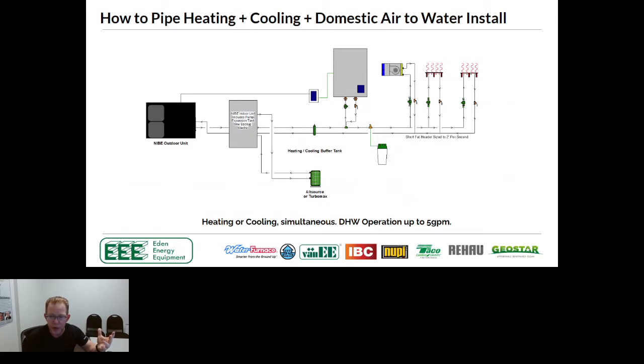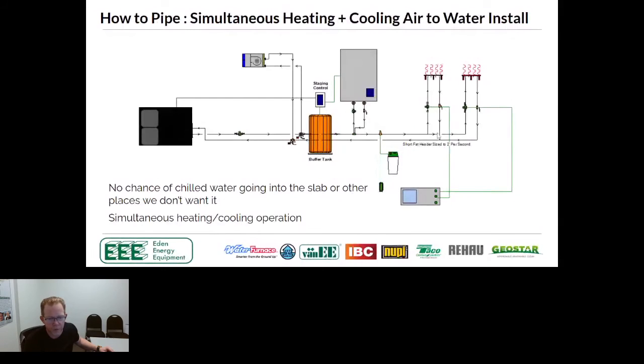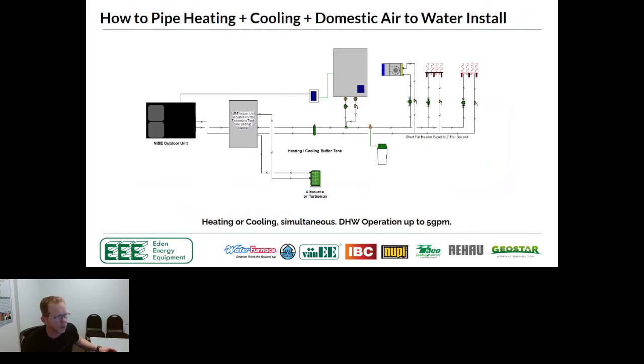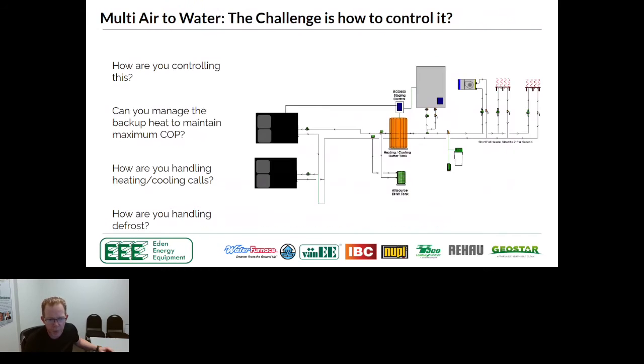This would be the example of how you would do the Enertech unit. The idea behind this is it has an integrated outdoor unit, integrated indoor unit, so you don't have to worry about a buffer tank. This unit does not require a buffer tank. And on top of it, we are prioritizing the load. So what happens is if the cooling calls, there is absolutely no way that we can pump chilled water into this slab. So if we look back at this drawing, if this tank is filled with hot water, then obviously we'll be putting hot water here, but you could potentially draw chilled water as well if these three-way valves weren't here. So in the case of the Enertech product, you actually don't have to worry about that. Indoor unit, outdoor unit, very, very easy to operate.